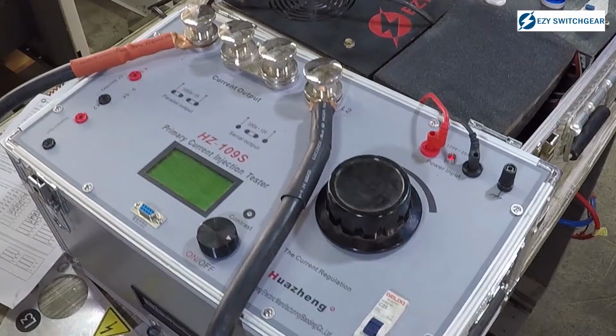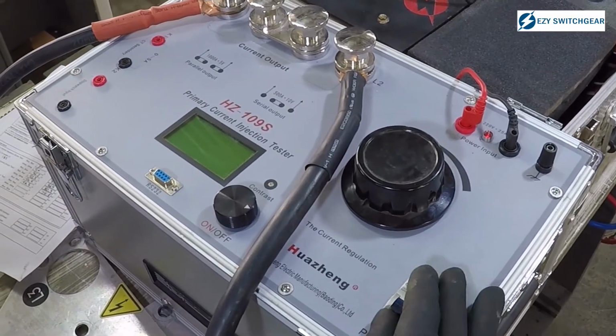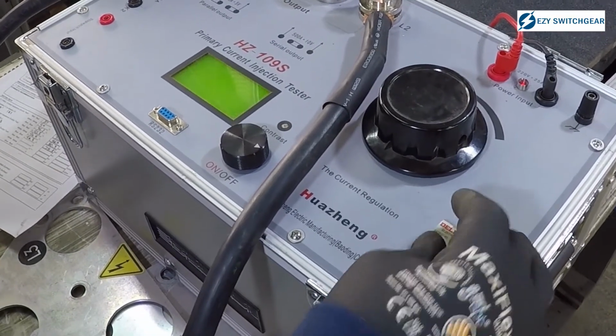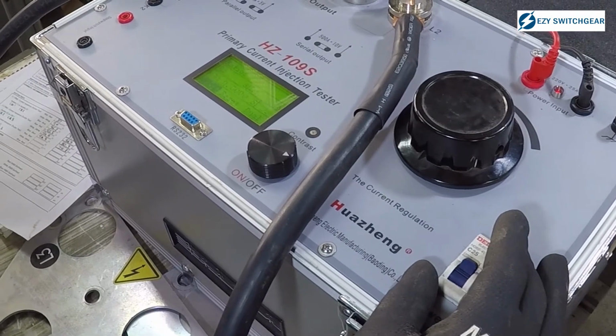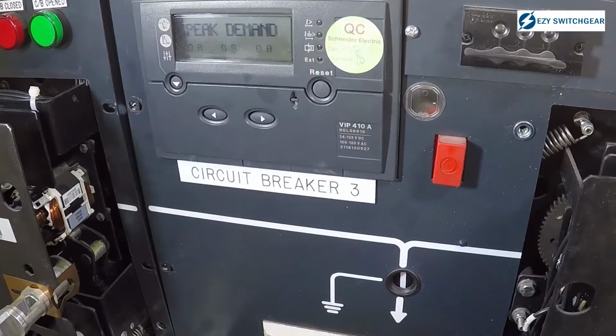The primary injection test is the third test, which is quite important. The primary injection test tests the whole circuit from your CTs all the way to your protection device, your tripping and your mechanism. The primary injection test and the speed test are done in conjunction. The primary injection test ensures that when something happens on the network, your switchgear will trip.